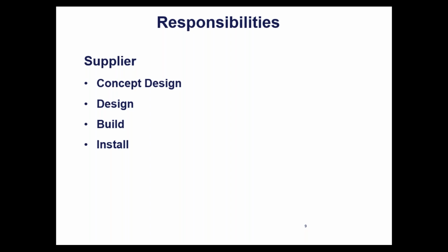When we're talking about ISO 12100, they talk only about suppliers. They say that you have to perform risk assessment at the concept design stage, at the design stage, at the build stage, and at the install stage. We are talking about when we are installing and debugging the equipment at the user's site, in the company that is going to use the equipment.